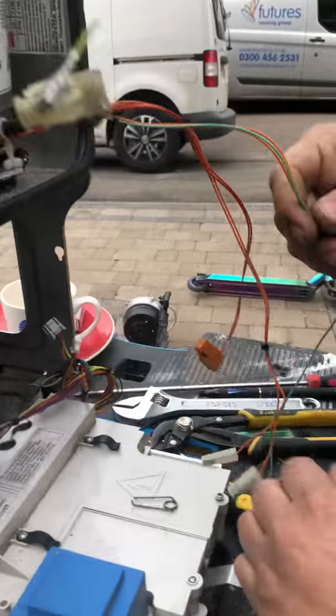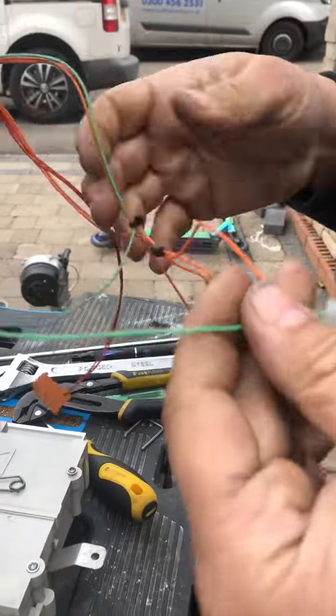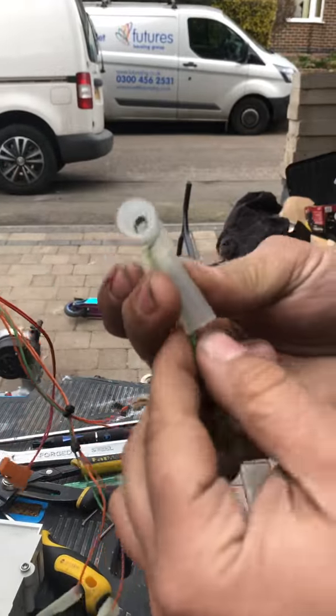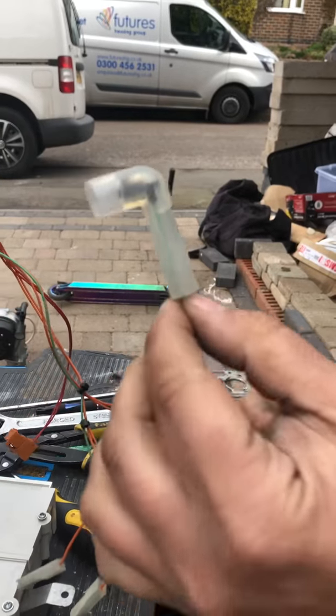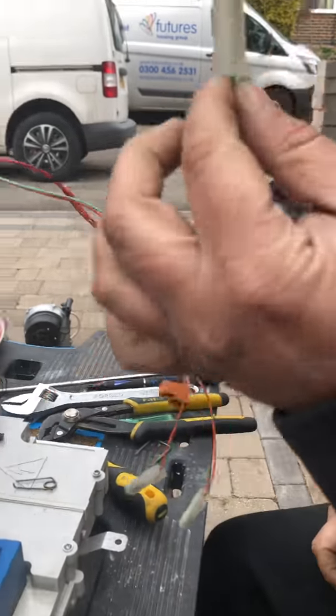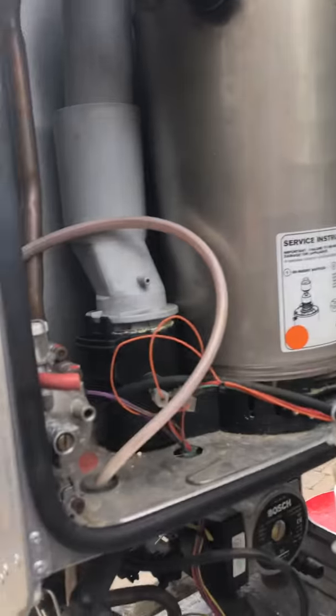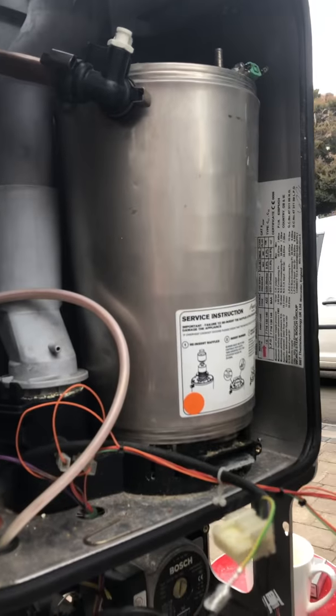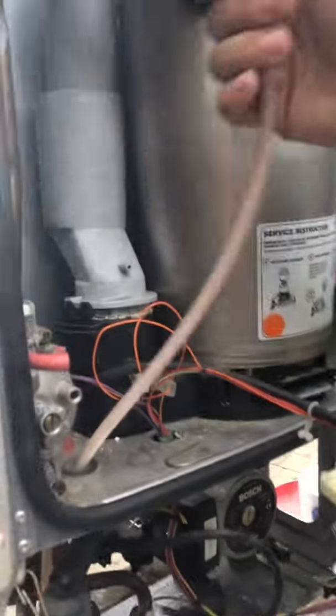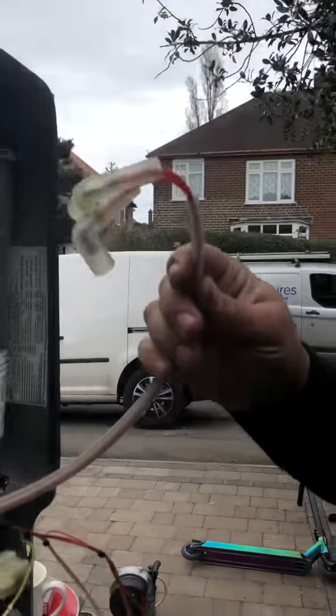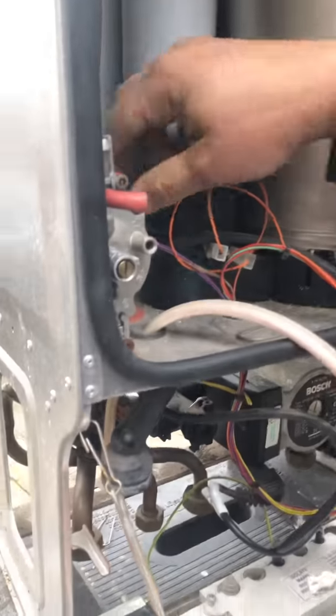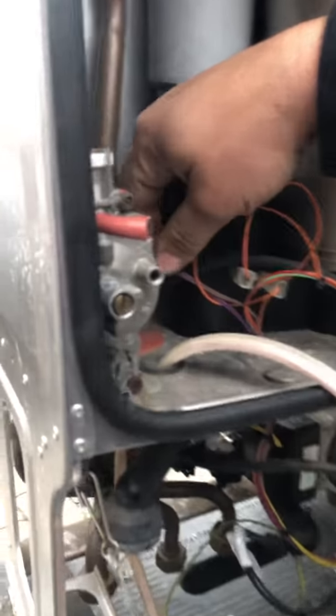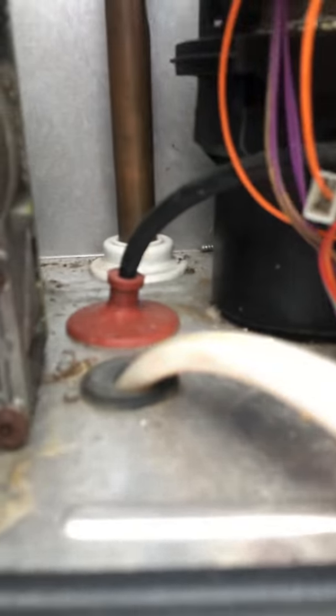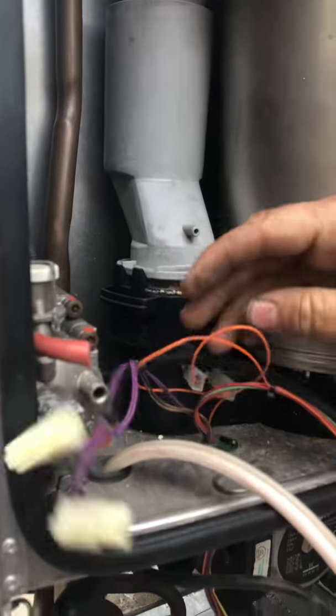The green one, there's only one green one, and that green one is the flame detection lead. Okay, so that won't fit onto anything apart from the spark electrodes, but they're red. We know they're red because they're in this big one here. Okay, now there's four purples here, and the purples go to your gas valve.